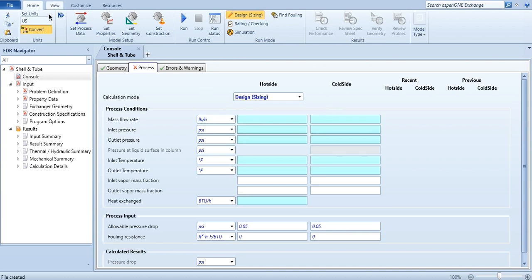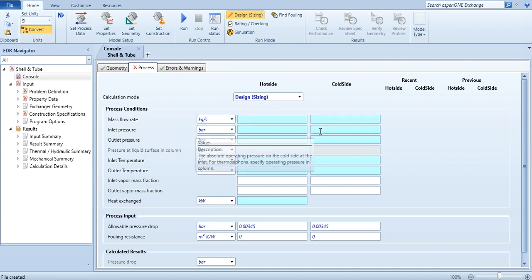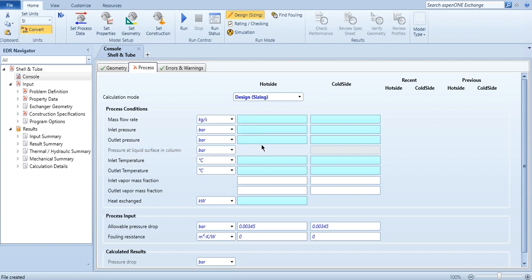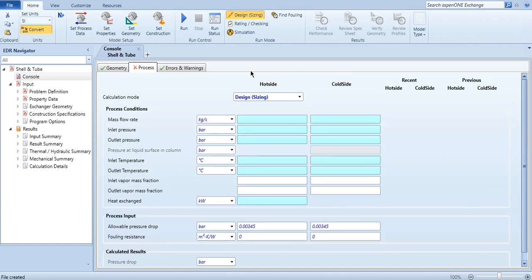Process conditions of hot side and cold side in design. Currently it is in English units, US units. You can click SI from here. It is the same pattern, same procedure of changing the unit set as that of Aspen Plus or even Aspen Hysys. And you can specify the flow rates, the pressures, inlet pressure, outlet pressure, inlet temperature, outlet temperature, vapor fraction, etc. as well. And again, if you want to specify the pressure drop, the fouling resistance, you can specify over here as well.